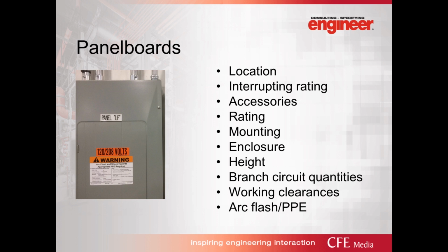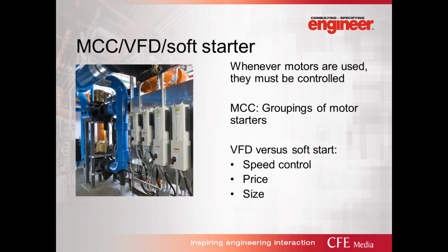There is a maximum requirement for panel board mounting height. Per NFPA 70 Section 404.8, the maximum breaker mounting height shall not exceed 6 foot 7 inches. Arc flash labels are required per NFPA 70E and OSHA.